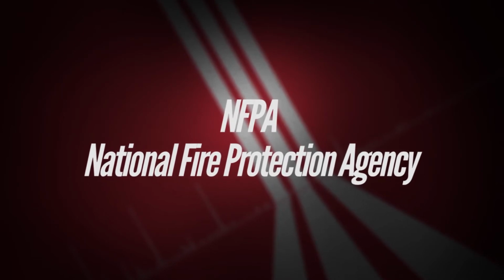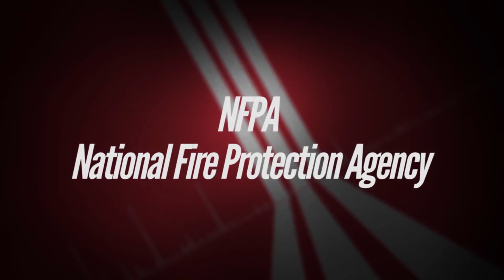There are three main bodies that set the standards and dictate regulations for commercial kitchen ventilation. These include the NFPA, or the National Fire Protection Agency. NFPA sets the national standards for exhaust hoods when it comes to installation and construction. They also regulate the fans, the canopies, and the fire protection systems. This standard is called NFPA Standard 96.